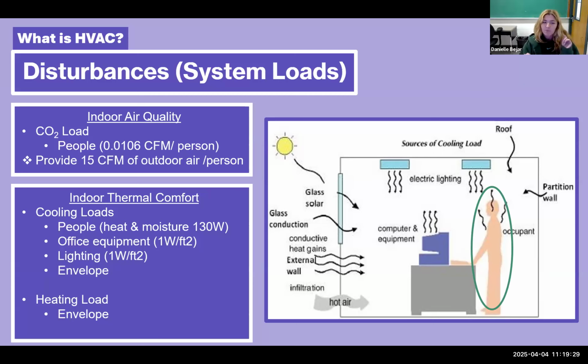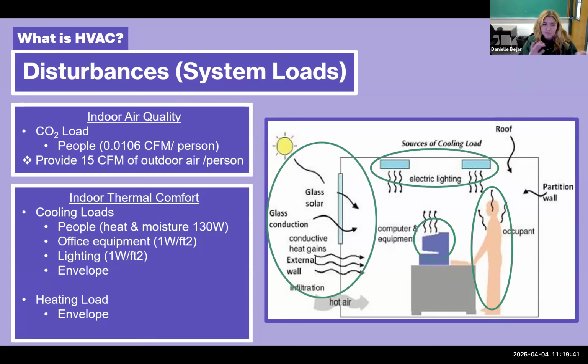For cooling loads, we have people, who emit heat and moisture, about 130 watts per person. Then we have office equipment, lighting, and heat transfer through the envelope. Office equipment and lighting are about 1 watt per square foot for each of those. Those are all our cooling loads, so our system has to provide dry, cool air in order to get us back to 75 degrees Fahrenheit, 50% relative humidity. And then for heating load, we can have heat transfer through the building envelope creating that heating load. So our system would have to provide hot air.